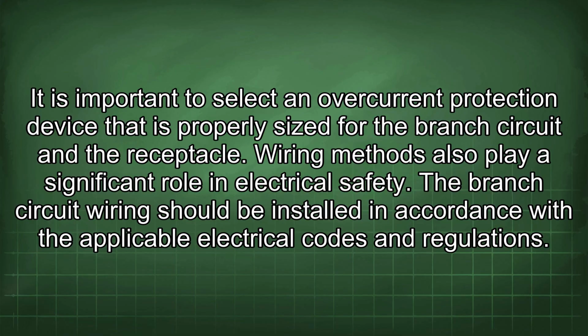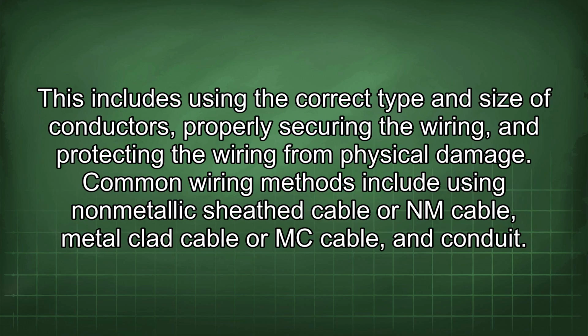Wiring methods also play a significant role in electrical safety. The branch circuit wiring should be installed in accordance with the applicable electrical codes and regulations. This includes using the correct type and size of conductors, properly securing the wiring, and protecting the wiring from physical damage. Common wiring methods include using non-metallic sheath cable or NM cable, metal-clad cable or MC cable, and conduit.